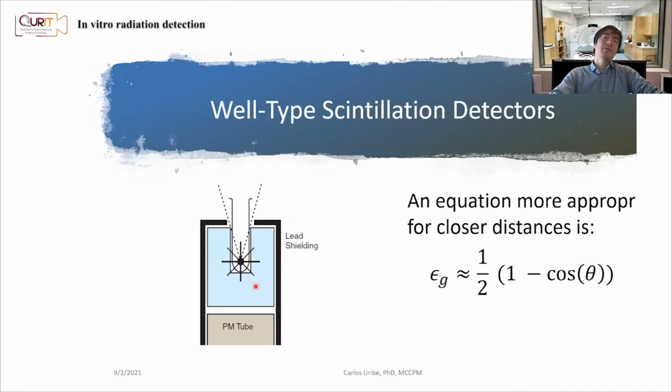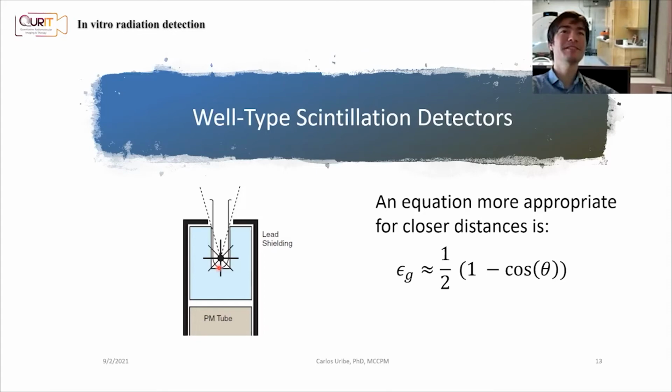Now we have a similar concept. You have a well-type detector, but instead of a gas, we place a scintillator, for example sodium iodide, an inorganic crystal, which is a higher density material with a higher Z value. So the probability of interaction goes up. Putting a scintillator material there instead of a gas makes the detector more efficient.